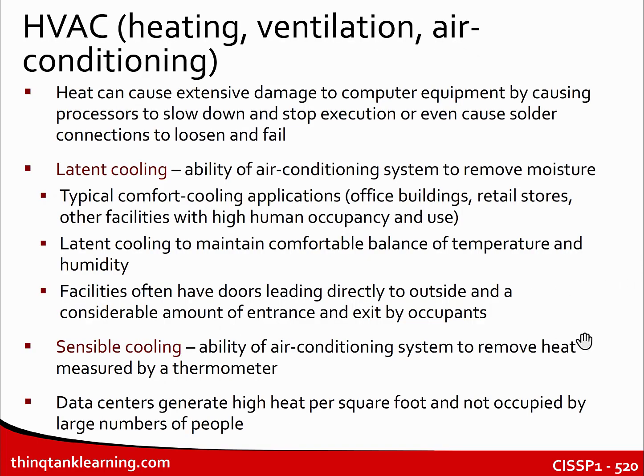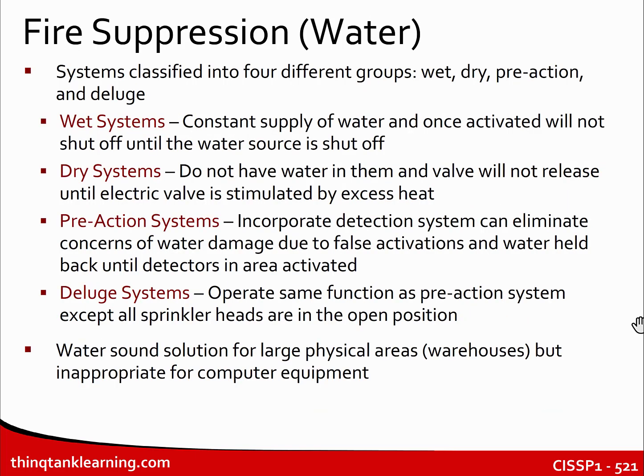All right. HVAC, heating, ventilation, and air conditioning, is also a consideration. Heat can cause a lot of damage, so you want to have cooling options. And they define two different types of cooling features here. Latent cooling is the ability of the air conditioning system to remove moisture, typically for comfort cooling applications like office buildings, retail environments, and so on. So we're maintaining this balance of temperature and humidity, which surprisingly enough, humans need. We need humidity. And sensible cooling is basically just removing heat. Data centers will typically use sensible cooling as opposed to latent cooling. So you might see some reference to those definitions on the exam.